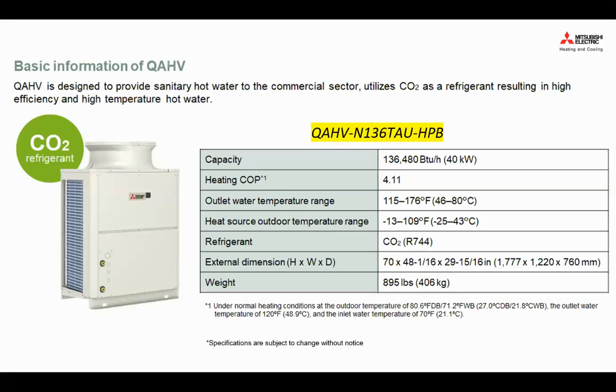So you can see here, here's some basic information on the QAHV. First of all, it is utilizing a CO2 refrigerant, and the nominal capacity is about 136 MBH or 40 kilowatts. The outlet water temperature can be between 46 to 80 degrees C, and it will operate between minus 25 to 43 degrees C. So suitable for our climates. And you can reach the COP of 4.11 if you have an entering water temperature of 20 degrees C and an outlet water temperature of about 48.9, 50 degrees C, or let's say 120 degrees Fahrenheit. So the COP will be able to reach 4.11.